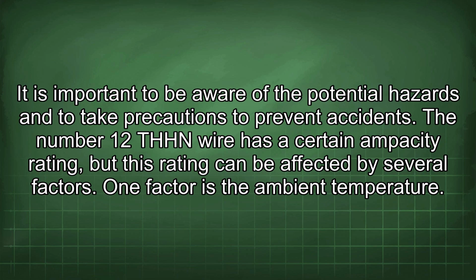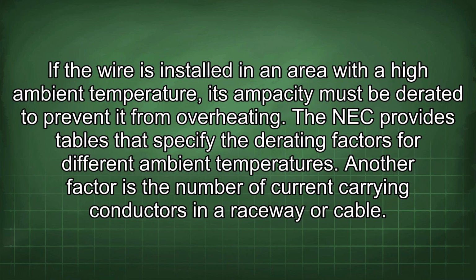The number 12 THHN wire has a certain ampacity rating, but this rating can be affected by several factors. One factor is the ambient temperature. If the wire is installed in an area with high ambient temperature, its ampacity must be derated to prevent it from overheating. The NEC provides tables that specify the derating factors for different ambient temperatures.